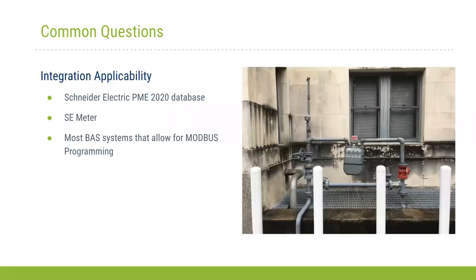Some common questions came up from our install at the Terminal Annex Federal Building. One was whether this can integrate with Schneider Electric PME, a database, SE meters, or any other BAS that allows for Modbus programming. The answer is yes. I'd definitely reach out to the vendor and ask about their experience, but we found that any BAS-related or Internet of Things device that can take Modbus programming, or any of the other protocols Sean spoke about previously, will work easily.